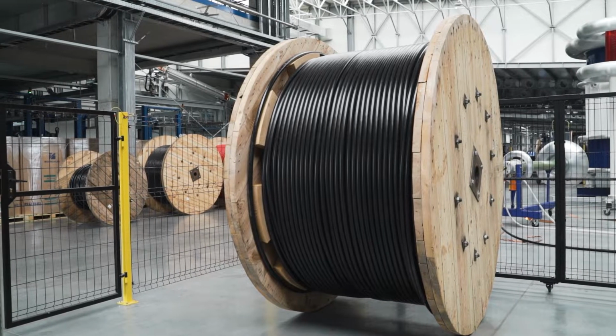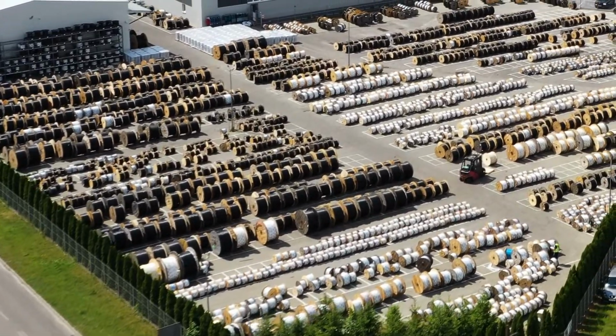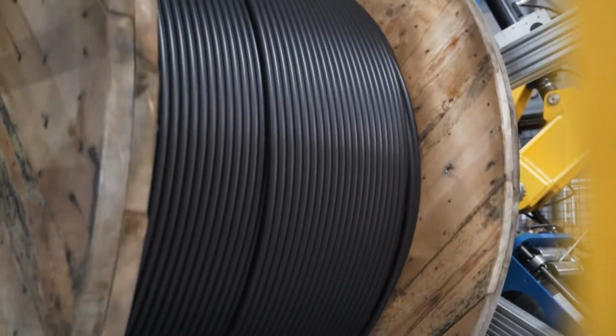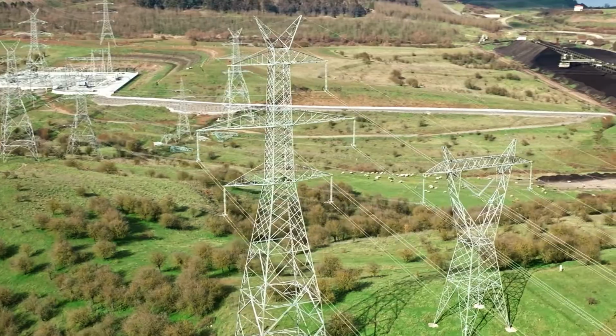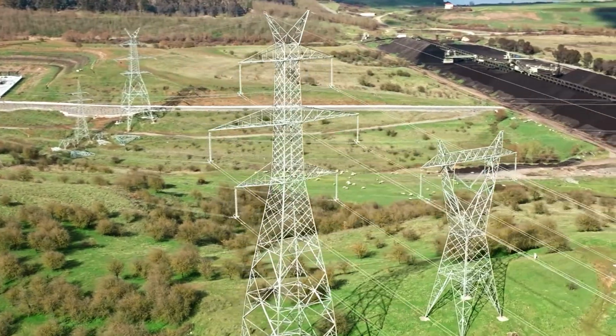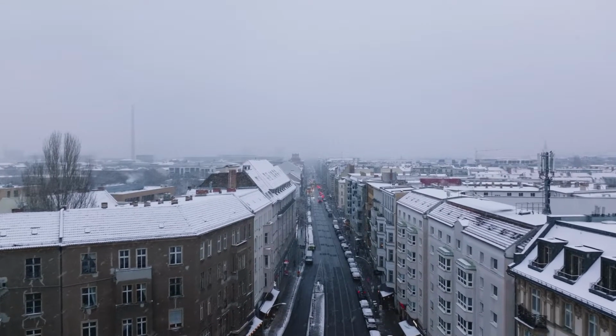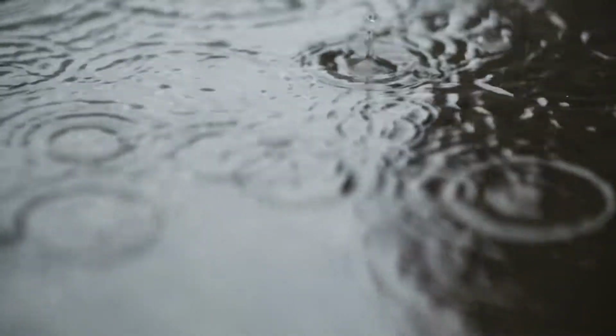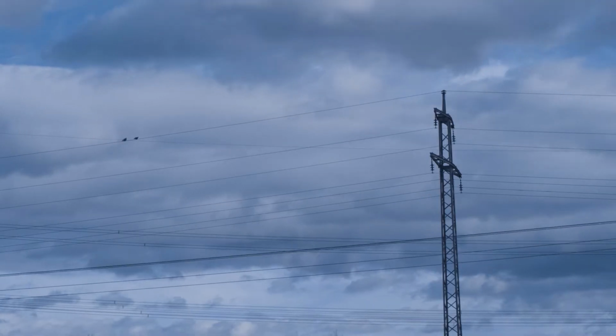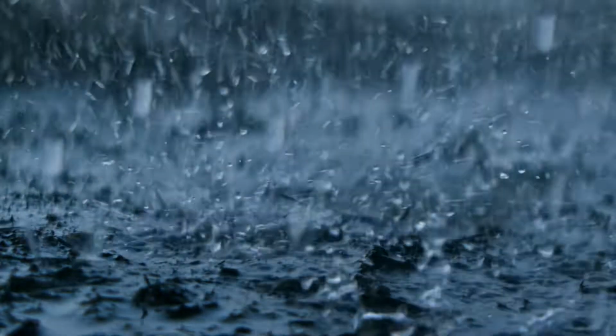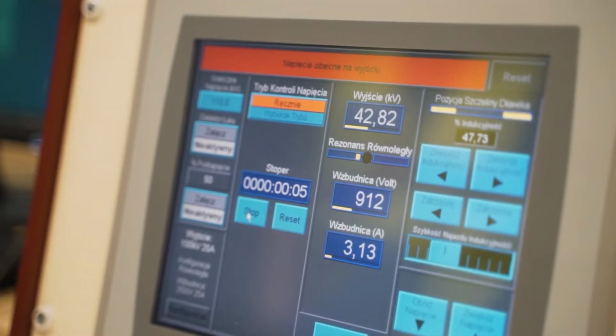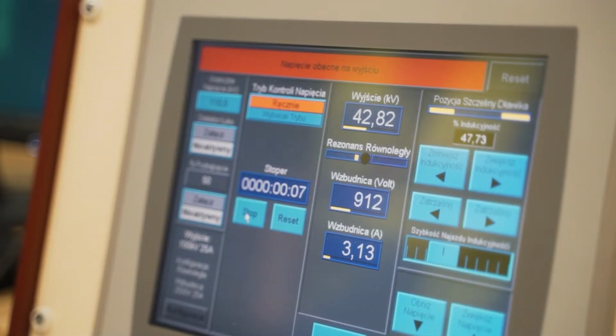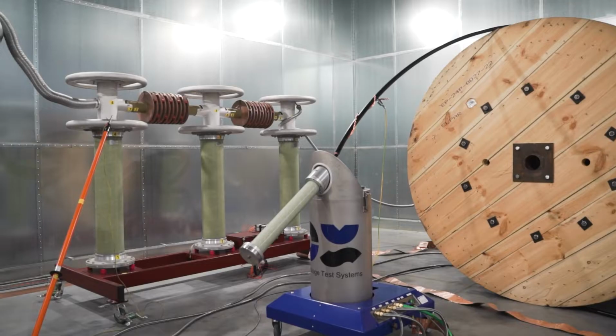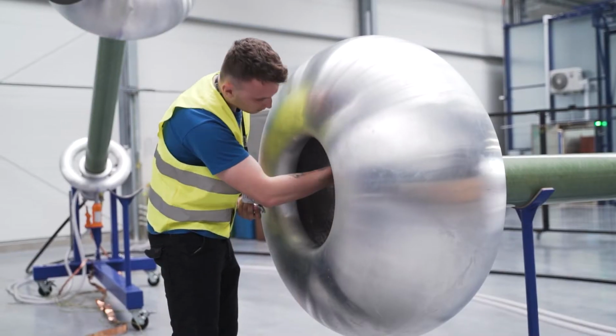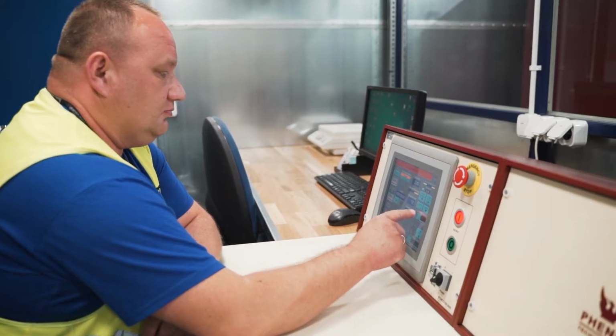Medium voltage power cables can be laid directly in the ground, special ducts, culverts, and in the air. If in special seals, they can be used in very demanding environmental conditions. They are designed to work with long-term load at a temperature of up to 90 degrees centigrade, and during short-term short circuits, they can withstand a temperature of up to 250 degrees centigrade.